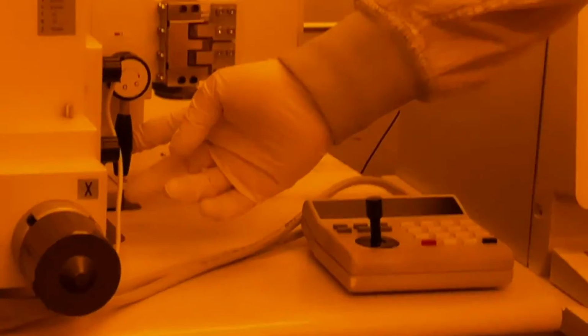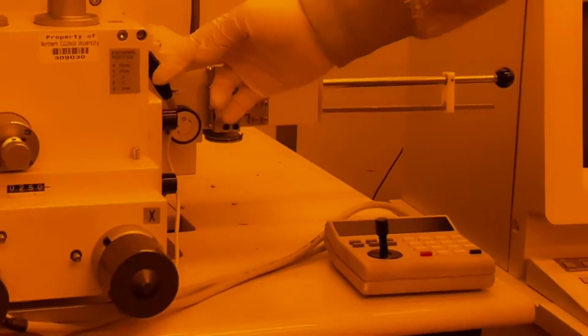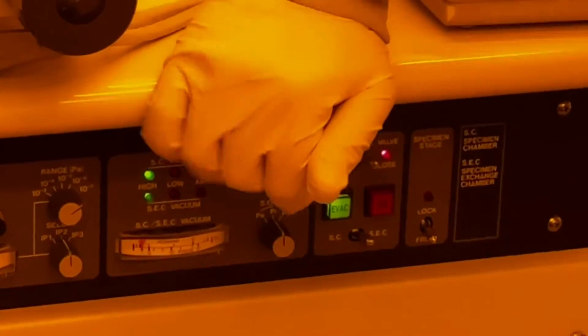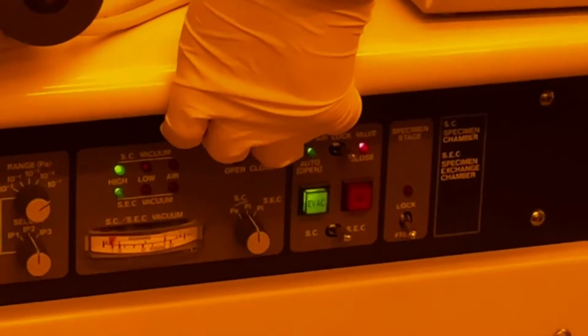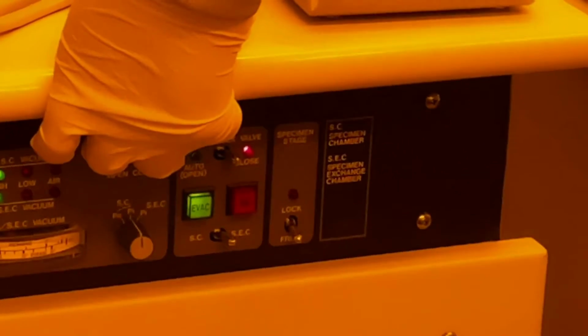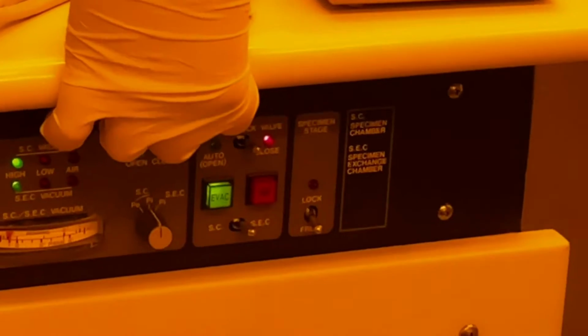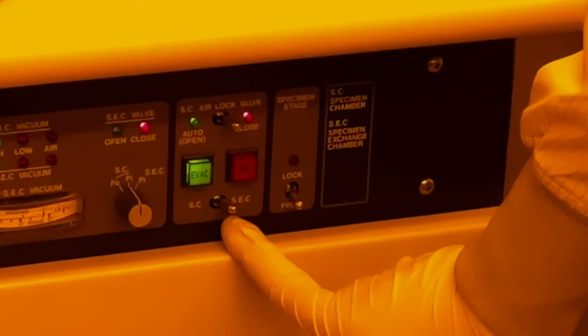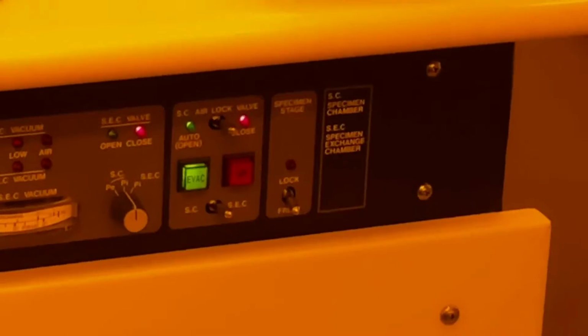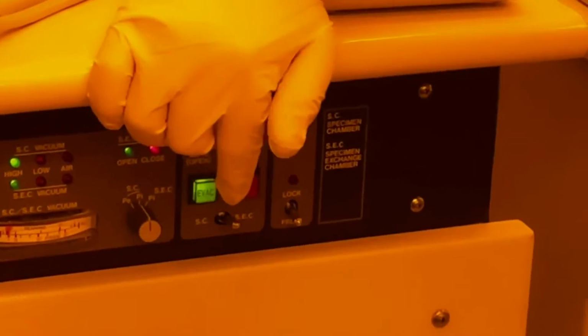Finally, on this section, we have the sample exchange valve. Right now, it's closed. This is an indicator that determines whether this mechanical valve here is open or closed. So as we open it, you can see that it now says that it's open. And then close it, vice versa. Now we have over here on this next section, the evac and venting system. So down here, you can switch between the sample chamber and the sample exchange chamber. And you can either evacuate it or vent it using these 2 buttons.